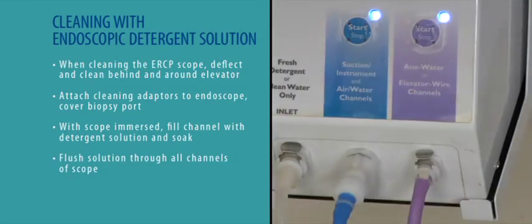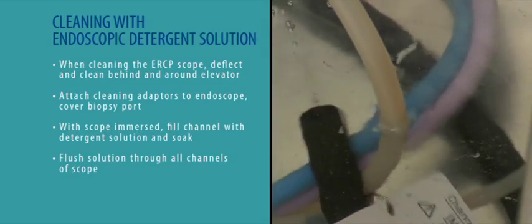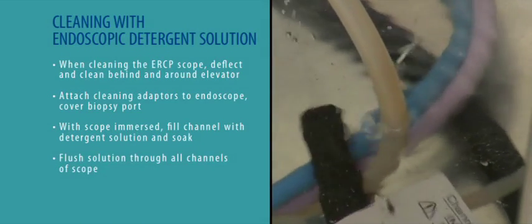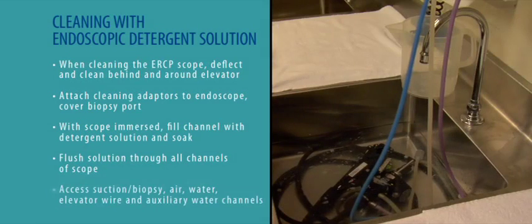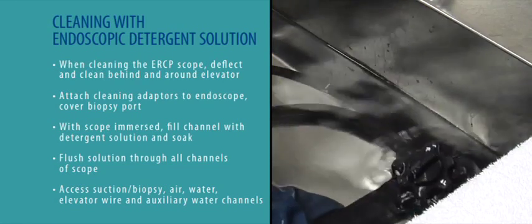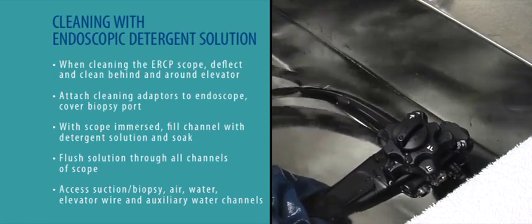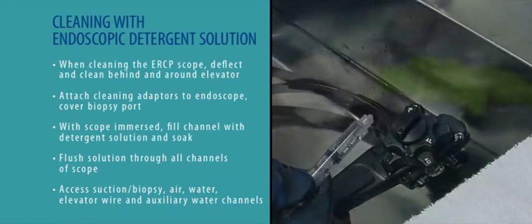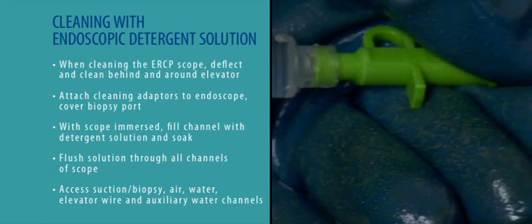Flush solution through all channels of the scope until no visible materials remain. Channels that should be accessed are suction biopsy, air, water, elevator wire, and auxiliary water channels. Because of its small size, a small caliber syringe, 3 to 5 cc, is needed to access the elevator wire channel.